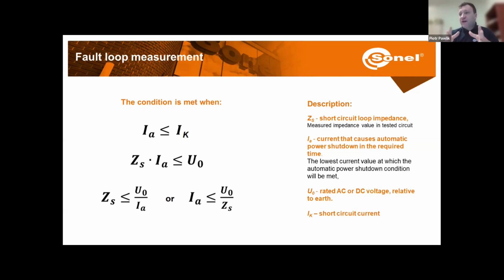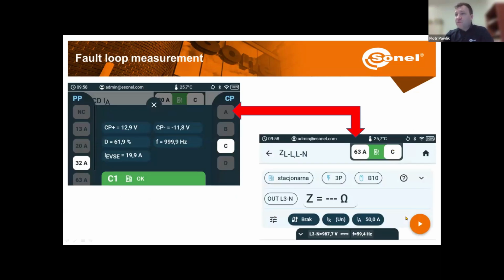Now, we are unable to measure fault currents directly. So for this reason, we are measuring the impedance of this fault loop. And we know what our supply voltage is. Then voltage over measured impedance will give us the value of fault current. With our meters, we can perform this measurement. We can also enter on the meter what type of breaker we have. So then the meter will calculate for us the fault current and will compare it with the triggering current of the selected breaker, evaluating the result for us. So everything will be in green if it's okay, and in red if the result is negative.